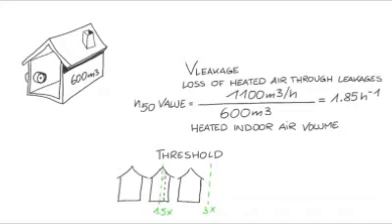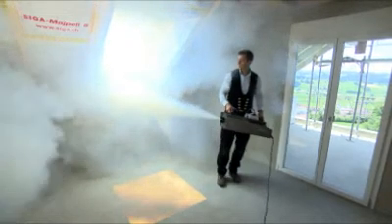In our example, this means the air change rate is too high because the architect planned a building with a ventilation system. The permissible limit value of 1.5 has been slightly exceeded. The craftsman has to search the leaks.